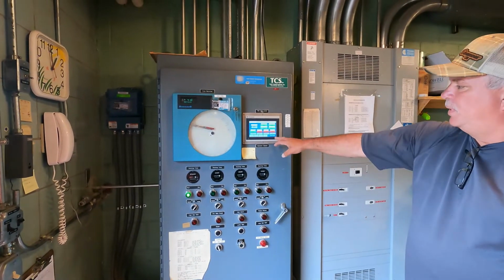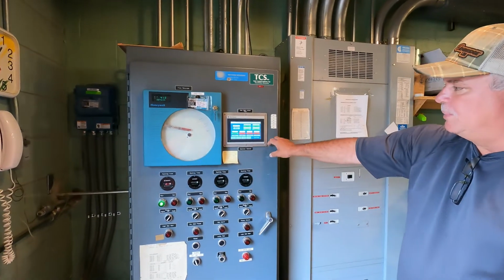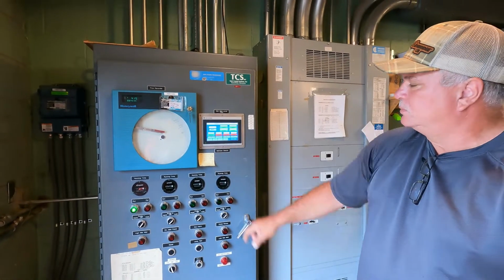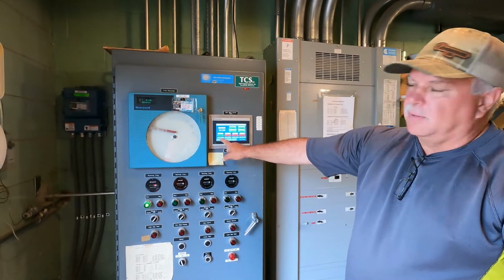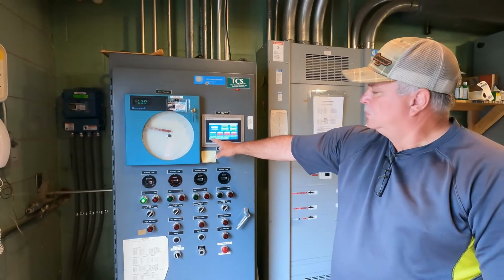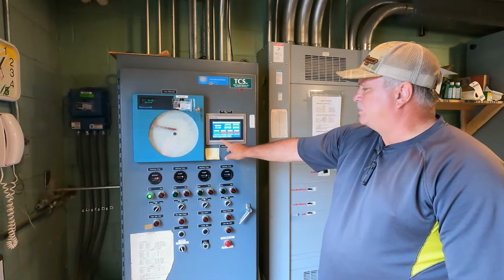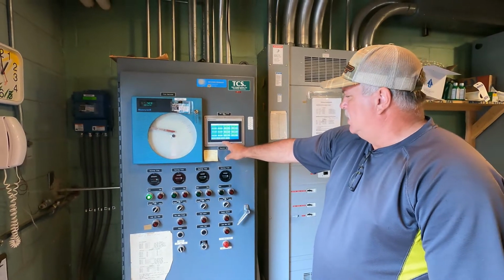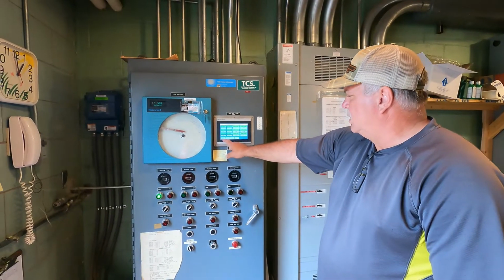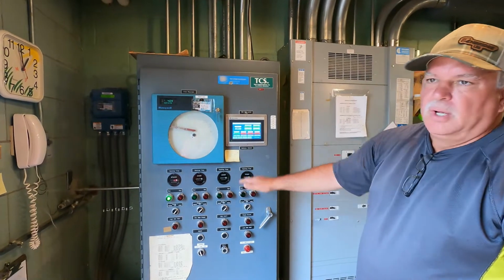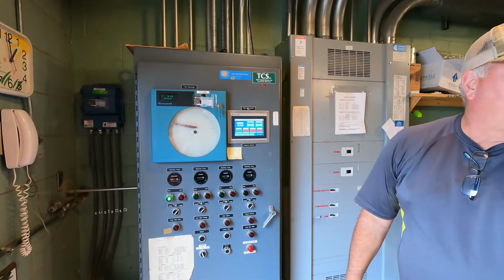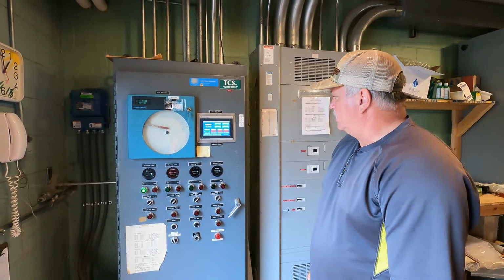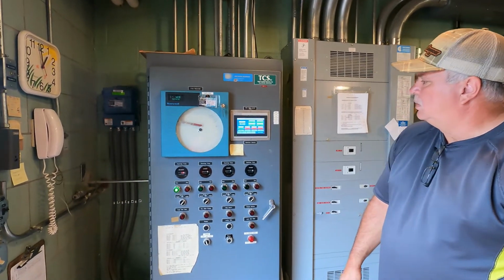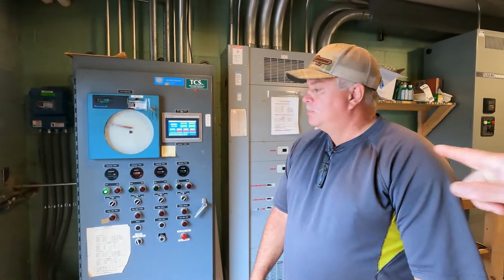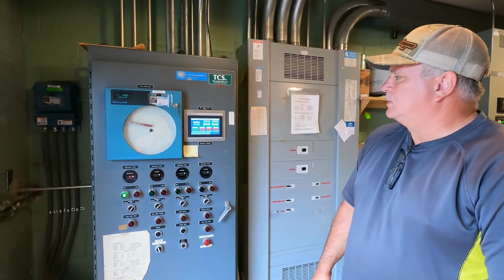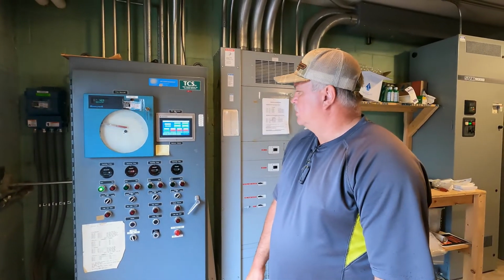And so the main Allen Bradley panel here shows us the level of the wet well. It'll show us the percentage of the hertz of the pump that's running. And we can go through and see the different speeds of the pumps, the levels, and have a little bit of control as the operator over levels and speeds of the pumps. So right now it looks like one pump is running, that's the lead pump, and the other 3 pumps are stopped. But will that alternate at some point?